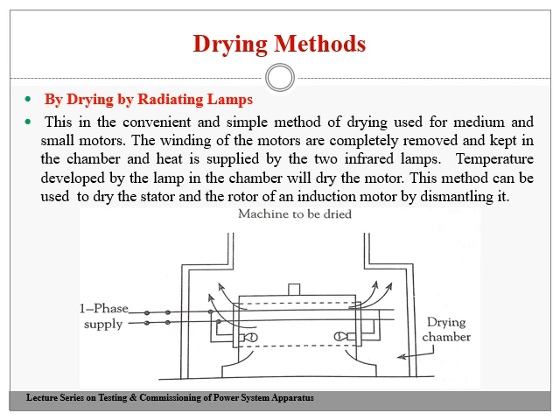This is the simplest method. Now we can dry out the stator separately and the rotor separately by giving the supply to the two bulbs. That's why we call them radiating lamps. In this also, the temperature should be kept well within the permissible limit of the withstanding ability of the insulation.